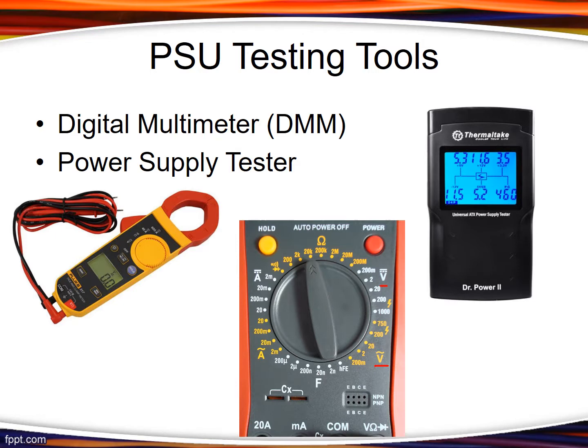If you turn it up too high, like if you set it to 1000 volts and try to test a 3-volt rail, you'll get a very small number that isn't meaningful because it has so many zeros in it—it'll just show 3 at the end of the scale. It won't tell you if it's 3.31 or 3.10, even though 3.31 is the expected mean. You have to look at the scale to see if it's within range, and if the range is set too high, you won't be able to see that detail. That's why you need the correct scale.